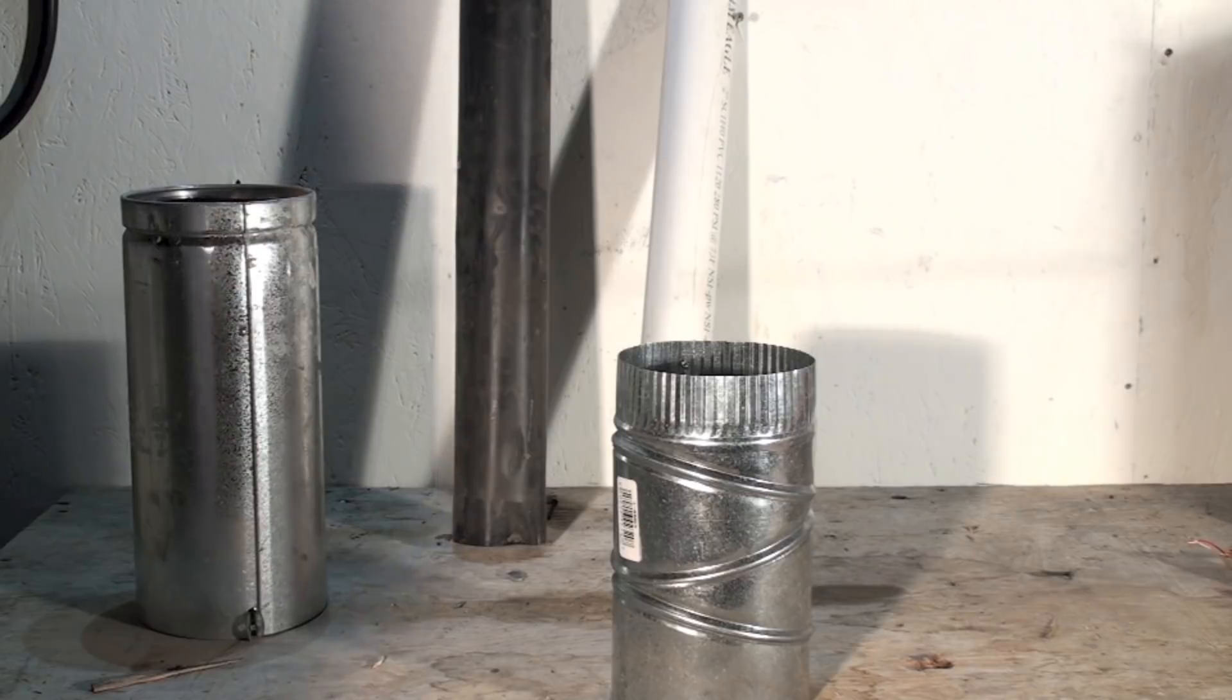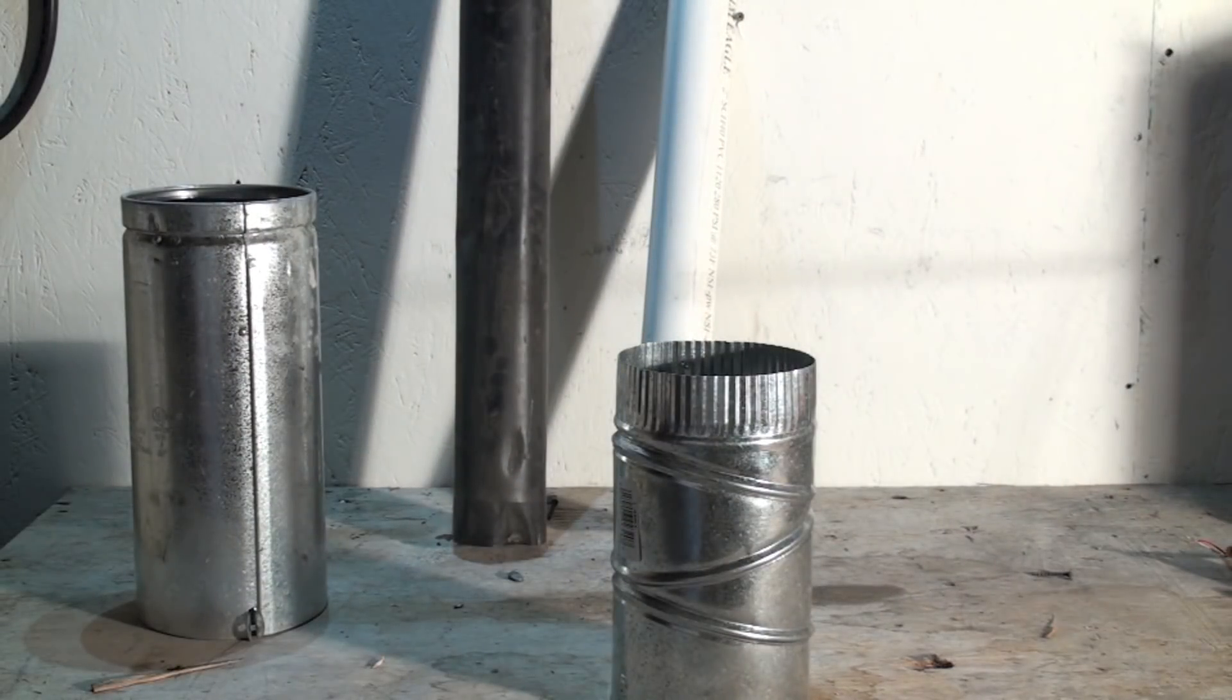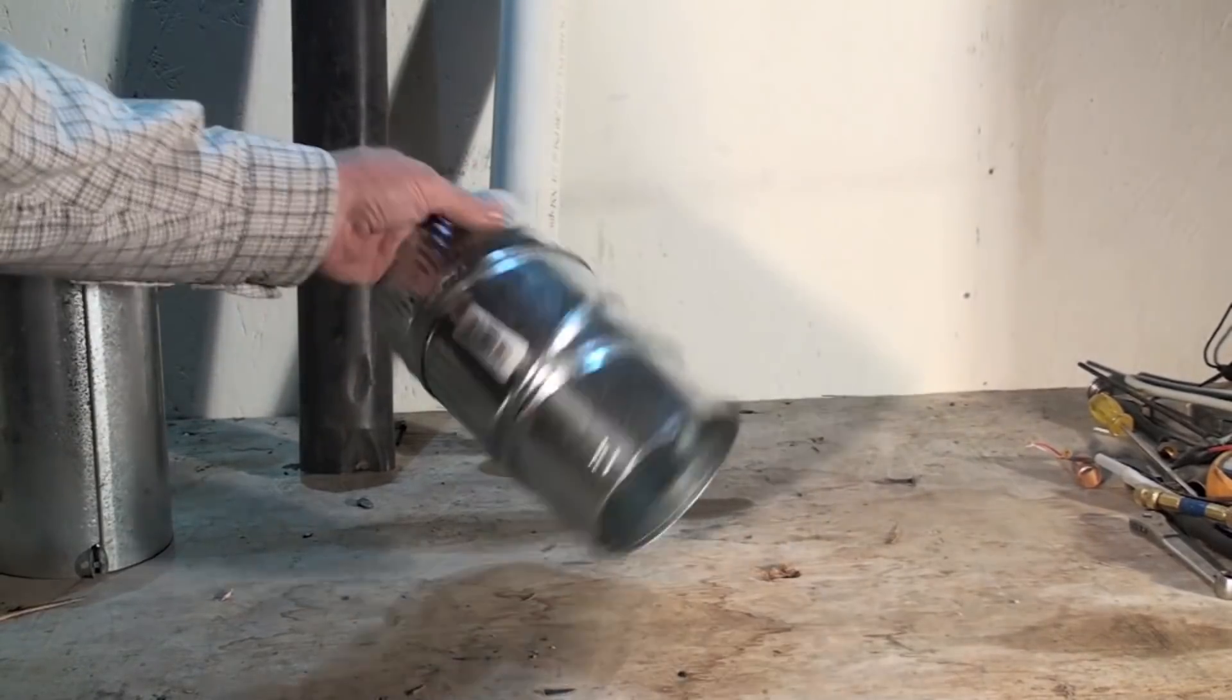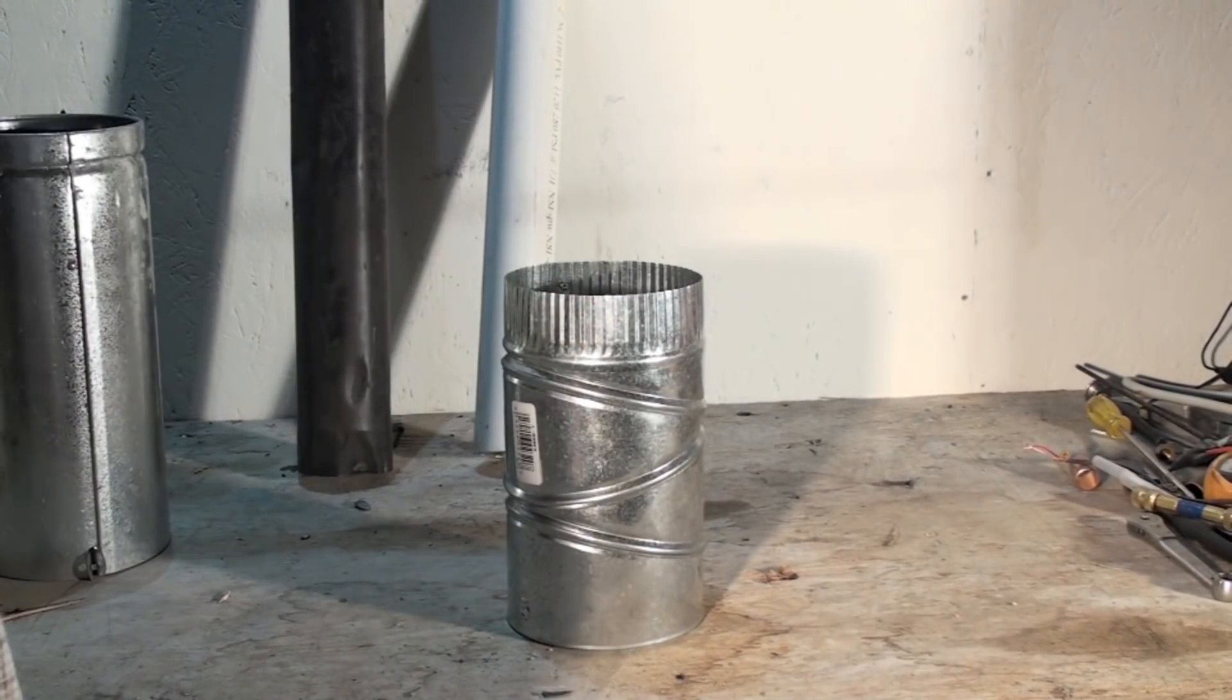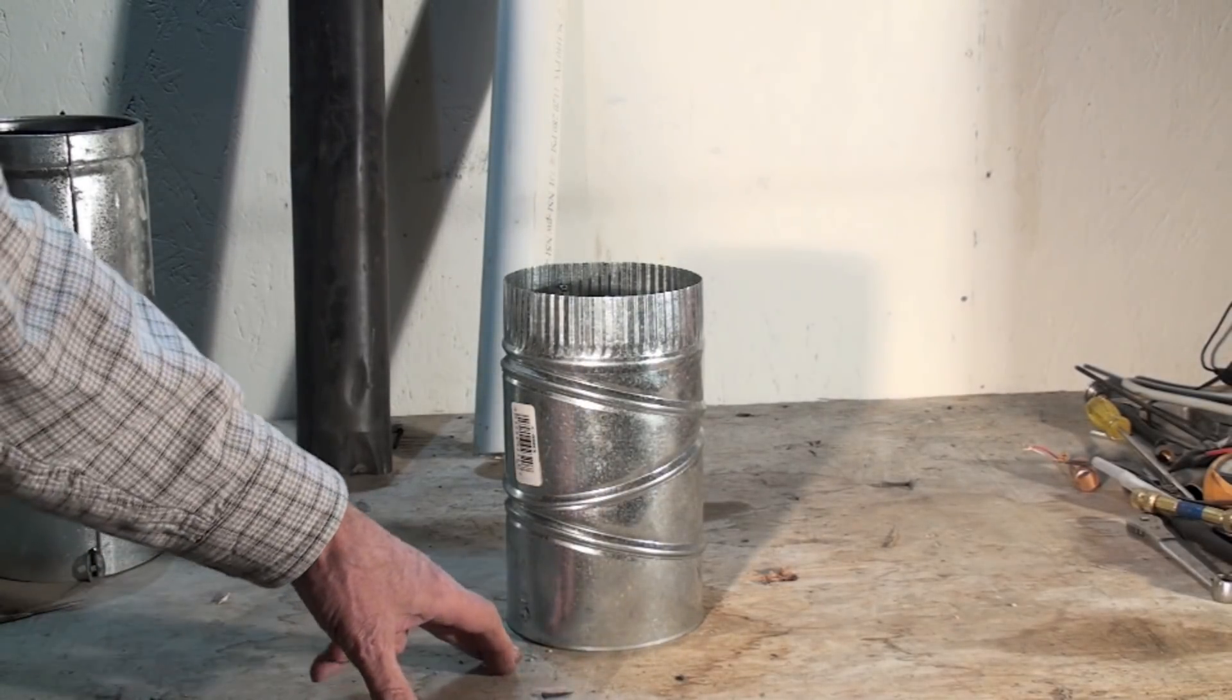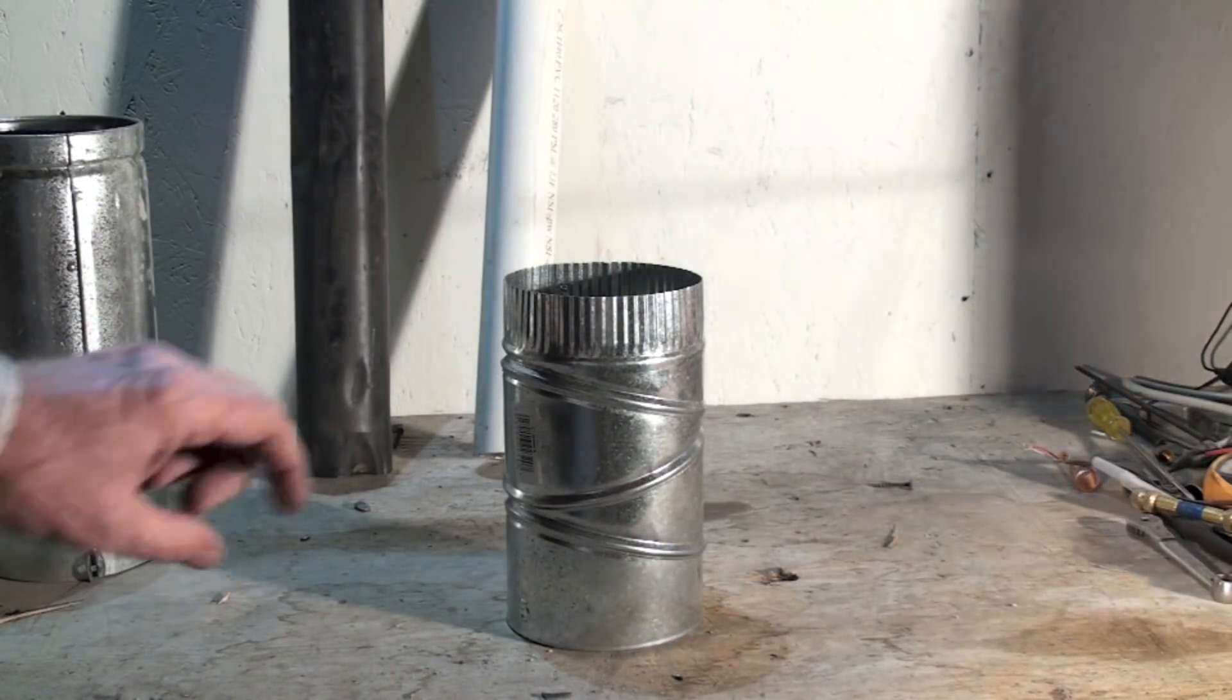This is one of the oldest vents. That is what we call C-Vent. C-Vent is nothing more than galvanized pipe that's single wall. There's a six inch clearance to combustibles. Now this is for gas furnaces only.